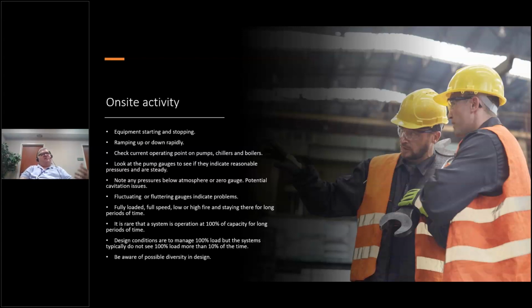Well, diversity allows for that because the load moves in the building. It's not going to stay at 100% all over the building. So there's a possibility that the load will shift from one part of the building to another. And so they designed to manage that by going to a certain level of diversity. But note that you'll see that sometimes. It was a trend. I don't know if it still is a trend, but it still affects what you're looking at. You're expecting a 100% design, but you see something designed for 80%. But that can happen.